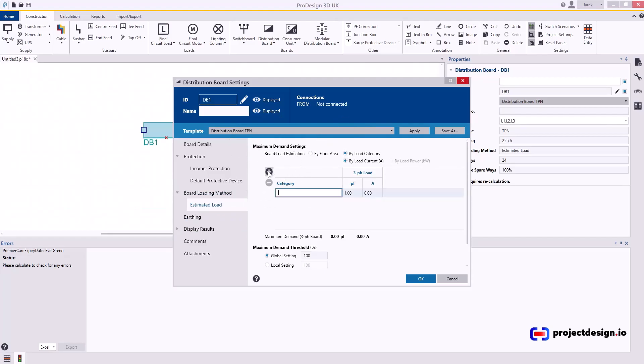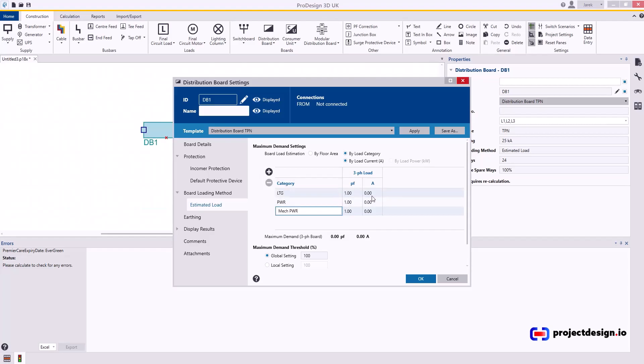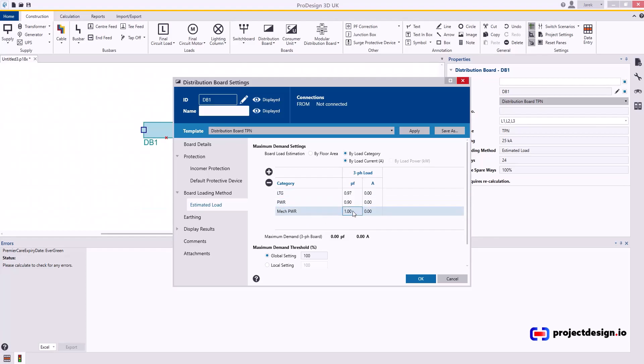Then you need to add categories. So I would typically add lighting, then I would add power, and if you want, maybe mechanical power, whatever you prefer. And then just type in—let's say lighting power factor would be 0.97, small power will be 0.9, and maybe mechanical power will be 0.89. Then add load as required in amps, so whatever.